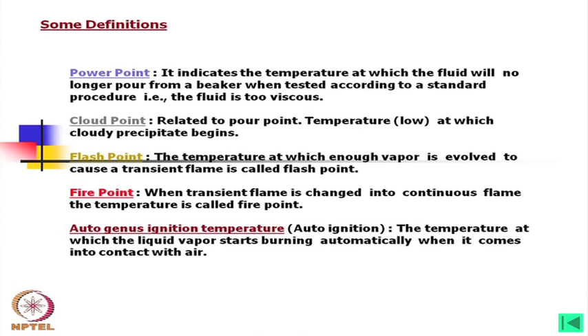In winter, you may find that oil temperature may be as high as 65°C, whereas the ambient temperature may be within 20–25°C. So we have to maintain this temperature for the safety of the machines as well as for performance, because if the temperature changes, viscosity will also change, which will affect the operation where very accurate control is needed.